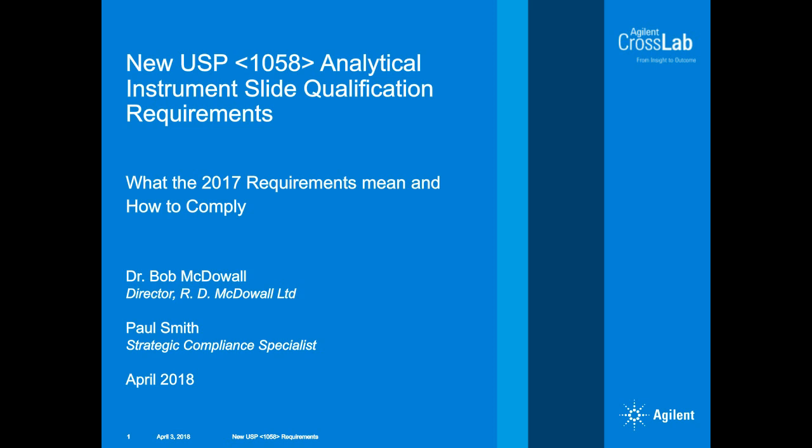Now, with the CDS system, which is category 4, in addition to the URS, or as an associated document, you need to document the configuration settings, the system policies, and also the access privileges for each of the user groups that you set up.